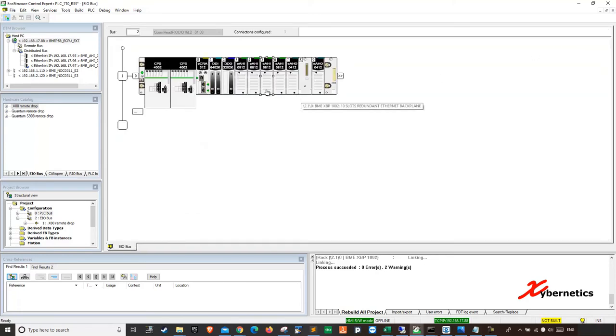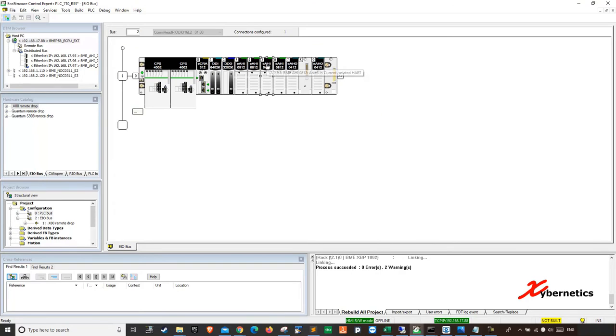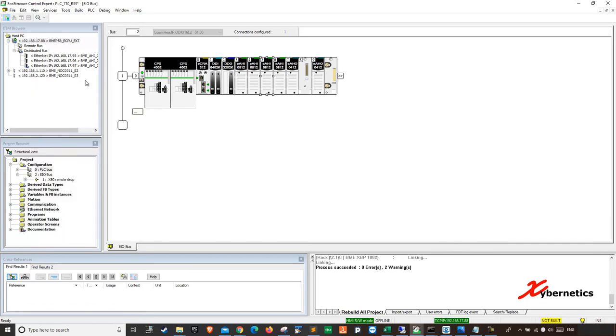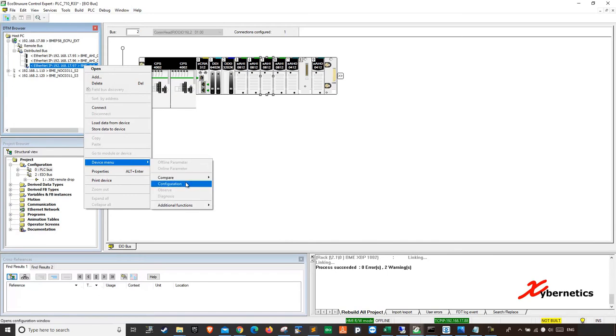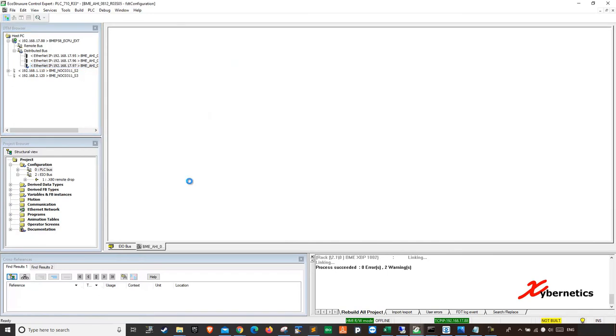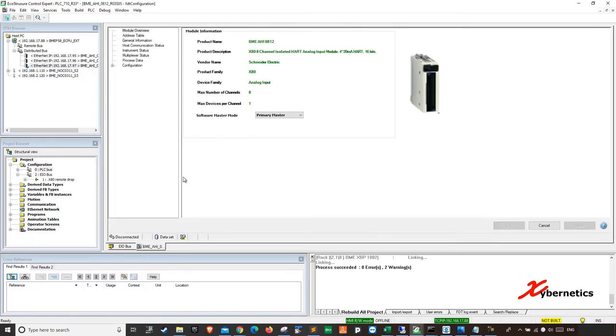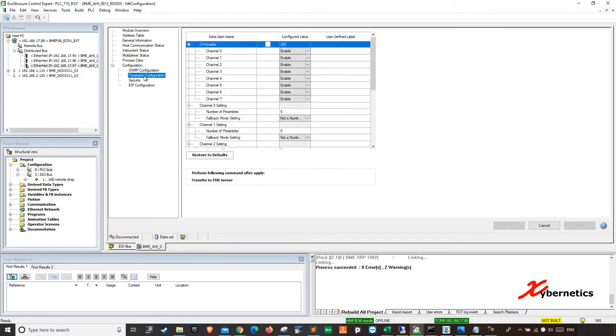So once that's done, you can close this. Next, we're going to disable all the HART on this card, mainly because we are not using HART. We're using 4 to 20 milliamps. So it's best practice to disable it. Just going to close this hardware catalog here. So if you go in here, right click this, device menu, configuration. Once you get into configuration, go expand your configuration again here and then go parameter configuration.